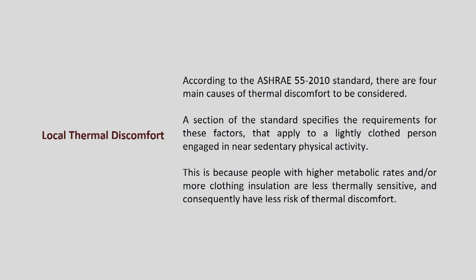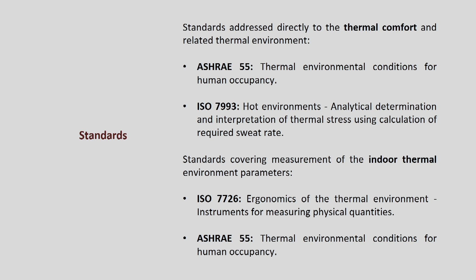Now let me talk a little bit about the standards. We have a variety of standards. ASHRAE 55 covers thermal environmental conditions for human occupancy. ISO 7933 covers hot environments, the analytical determination and interpretation of thermal stress using calculation of required sweat rate. So these are mainly on thermal comfort. For the indoor thermal environment, we have ISO 7726, which covers the ergonomics of the thermal environment and instruments for measuring physical quantities, and ASHRAE 55 again, thermal environmental conditions for human occupancy, which is the same.